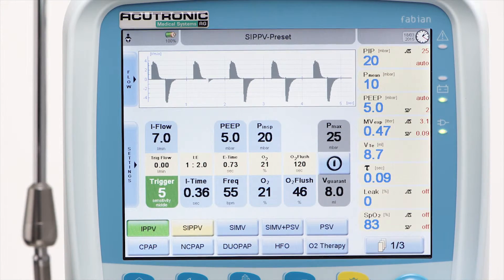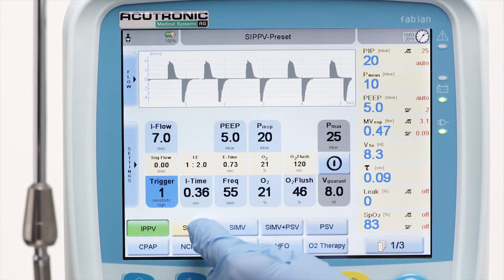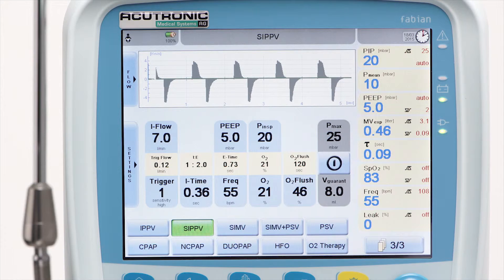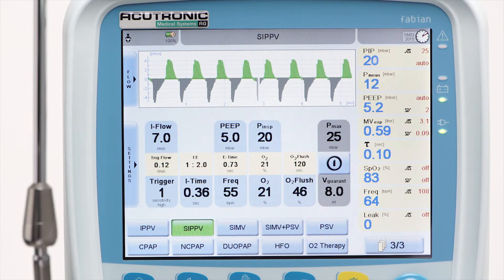on a scale from 1 to 10, with 1 being the highest sensitivity and fast response time, and 10 being the lowest sensitivity. Usually recommended is a trigger level between 1 and 3 for high sensitivity and fast response to the patient's inspiratory demand. Each inspiratory effort reaching the preset trigger threshold level will initiate a synchronized supported breath.